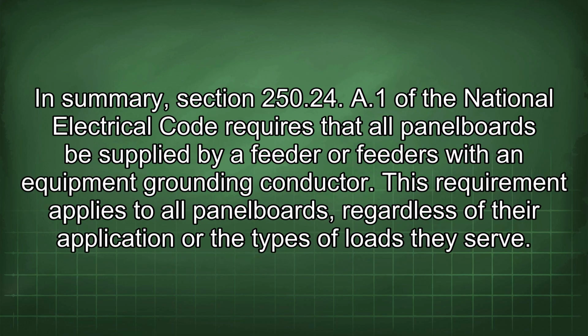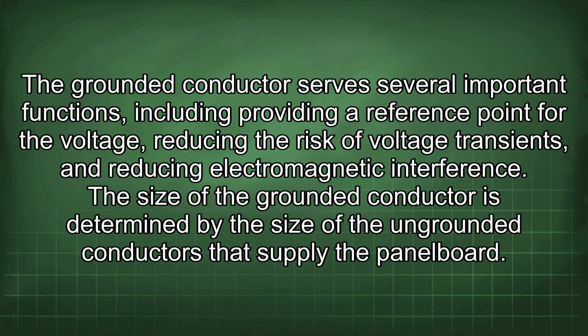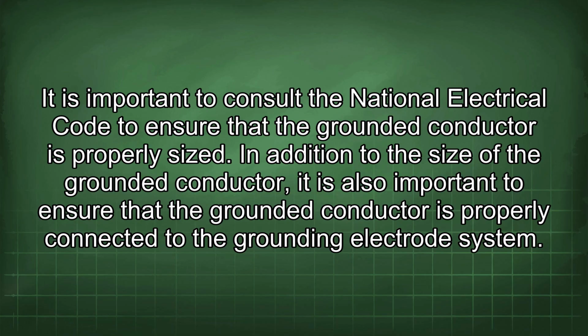In summary, Section 250.24(a)(1) of the National Electrical Code requires that all panelboards be supplied by a feeder or feeders with an equipment grounding conductor. This requirement applies to all panelboards, regardless of their application or the types of loads they serve. The grounded conductor serves several important functions, including providing a reference point for the voltage, reducing the risk of voltage transients, and reducing electromagnetic interference. The size of the grounded conductor is determined by the size of the ungrounded conductors that supply the panelboard. It is important to consult the National Electrical Code to ensure that the grounded conductor is properly sized.